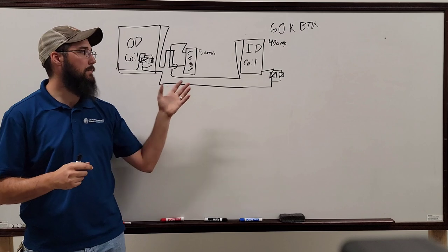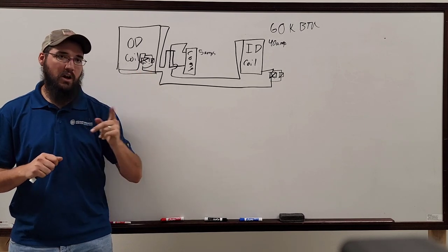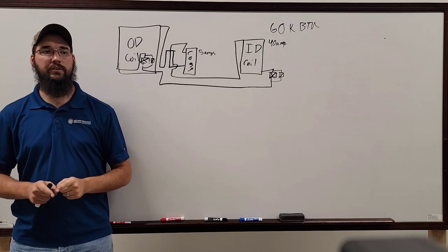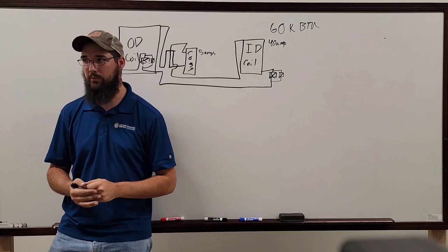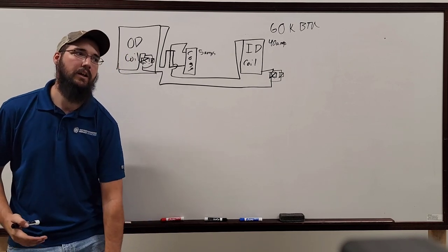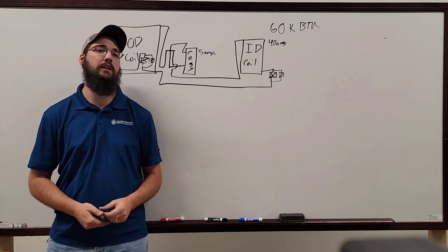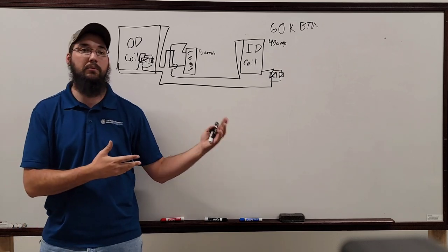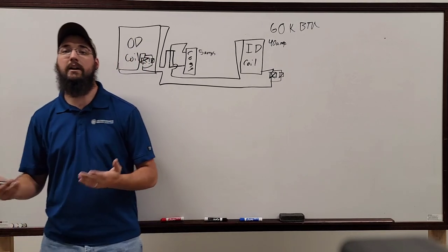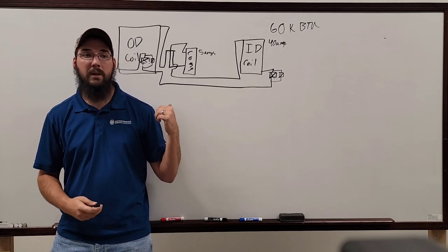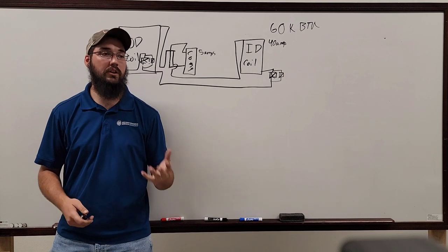Now, one of the critical things to understand before we go any further with a heat pump system is that if they're properly designed, they will rarely ever turn off. Let's say a residential customer, for example. Commercially, people don't really notice it that much, but on a residential level, say somebody is convinced to convert their electric heat system and install a heat pump this time because it's more efficient than the electric heater they had before. Well, a typical electric heat system may produce 100, 120 degree supply air coming out of that unit. A heat pump system is designed to maybe do 90, 95 on the top end, typically. So it's a lot lower discharge air temperature.